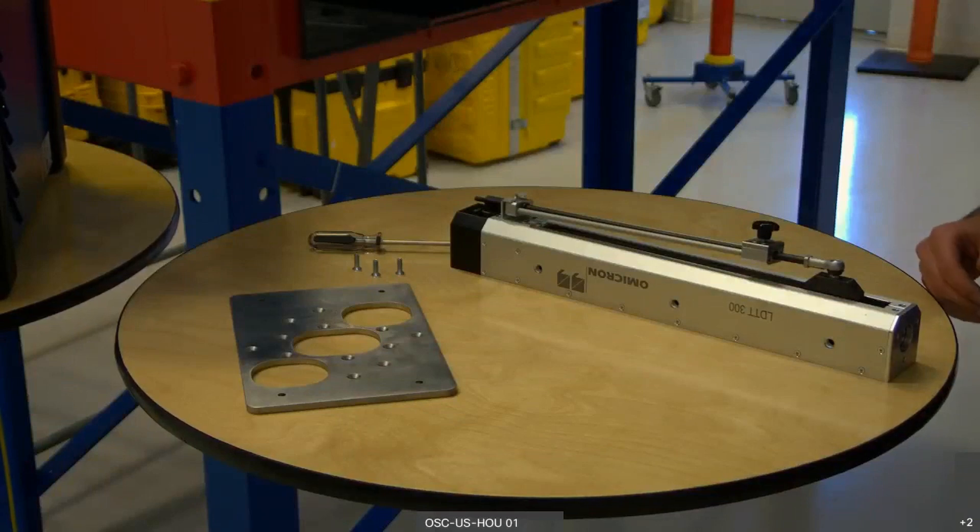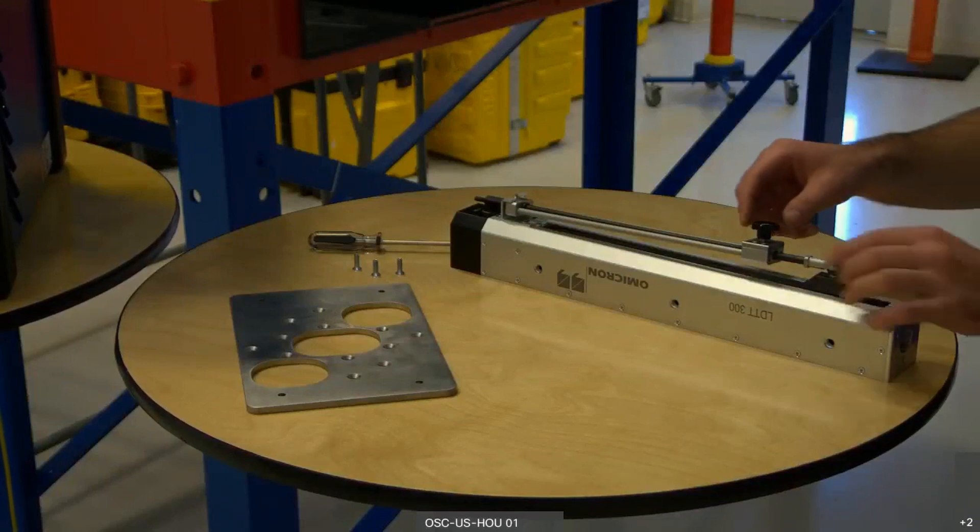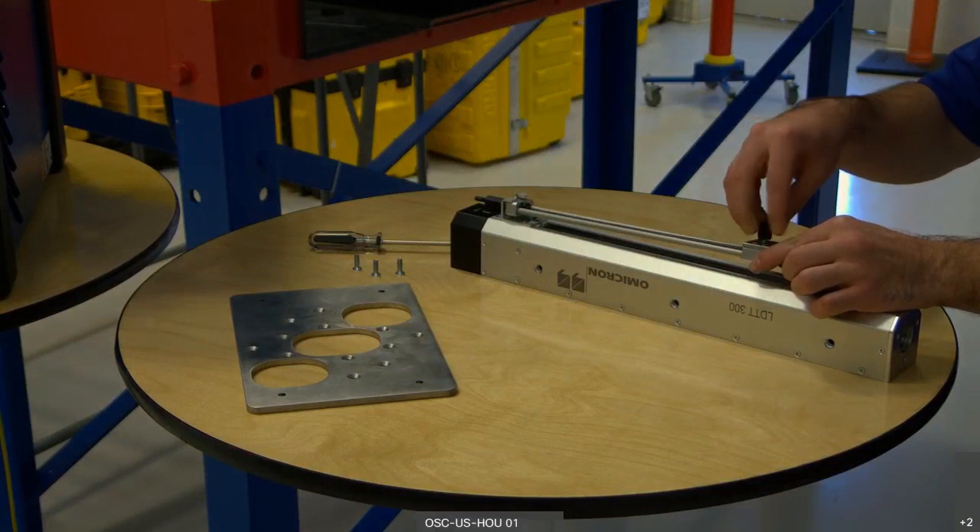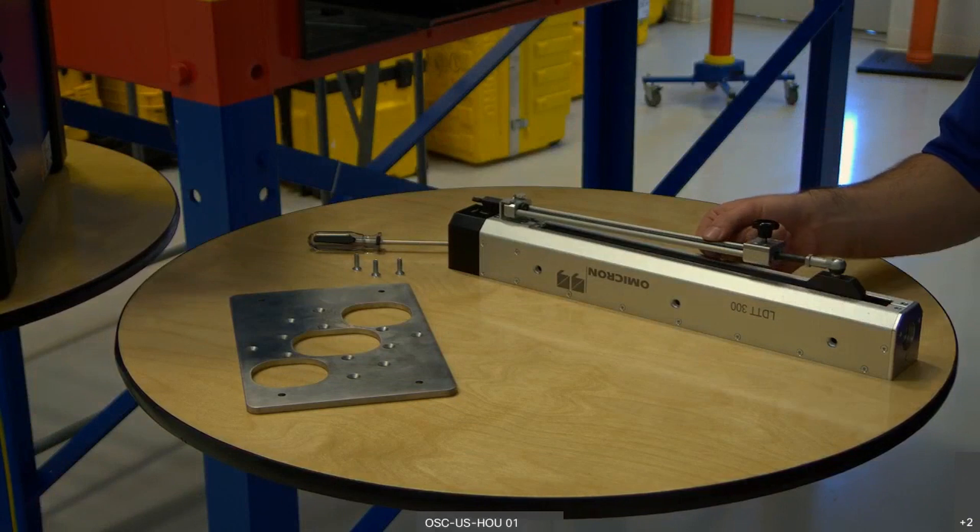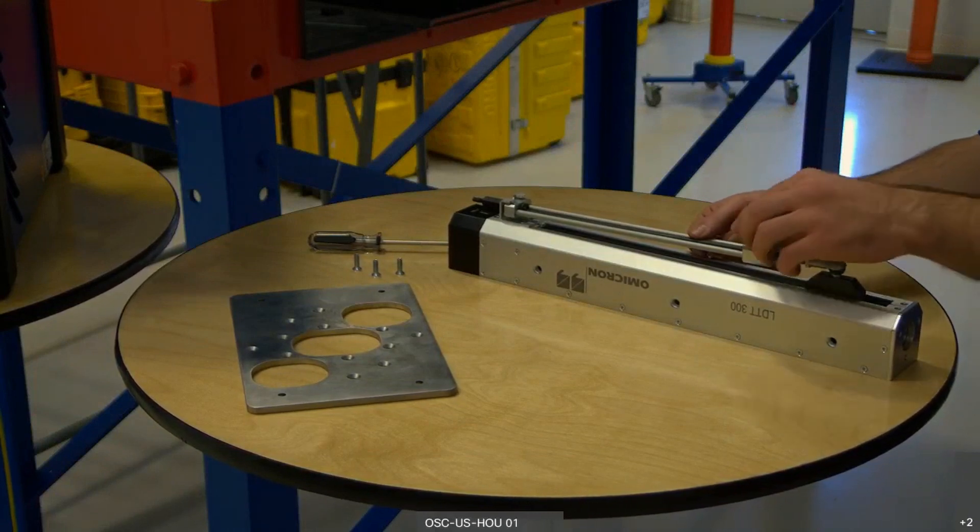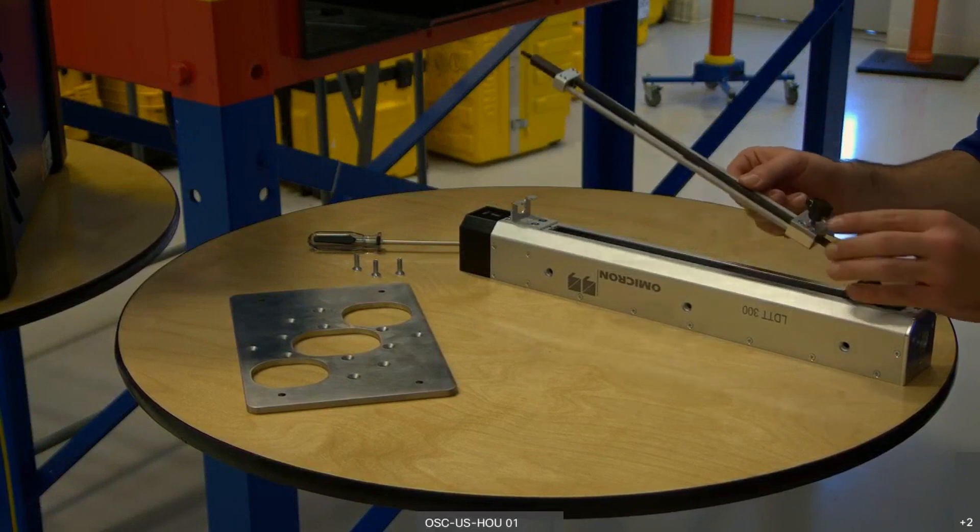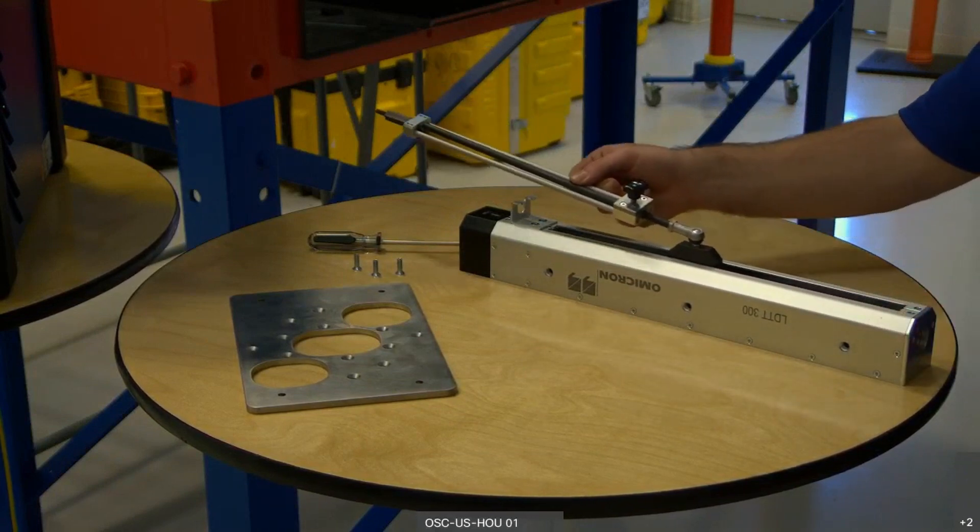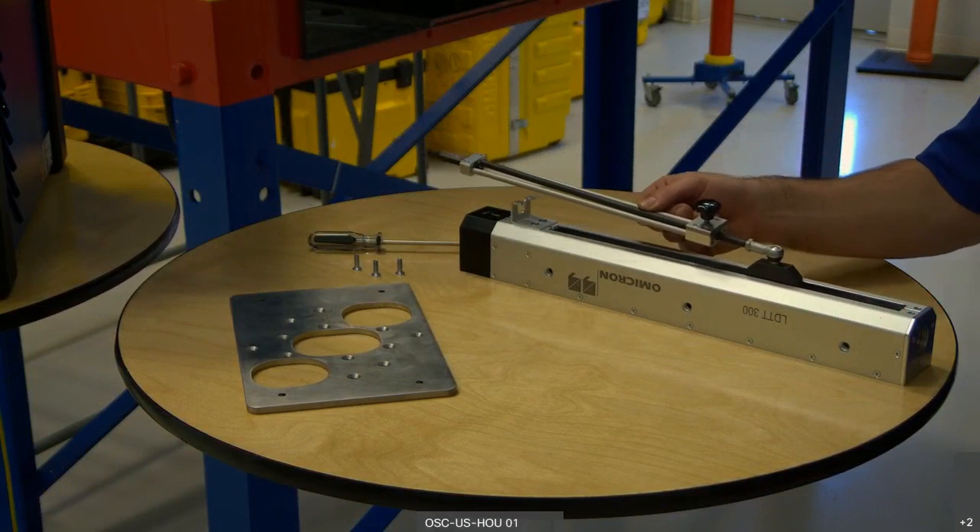So here we have our LDTT 300, and this rod right here is adjustable. The position it's in now is used for transportation so that it doesn't lock out, fall out of this place, and it's locked in. With it now loosened, we can raise it out of this position and move it to the necessary position to connect to the circuit breaker.